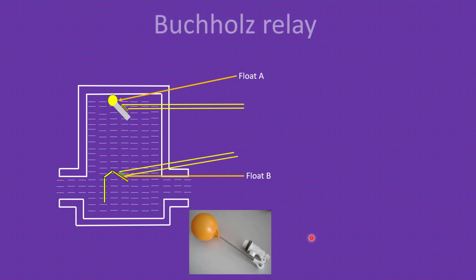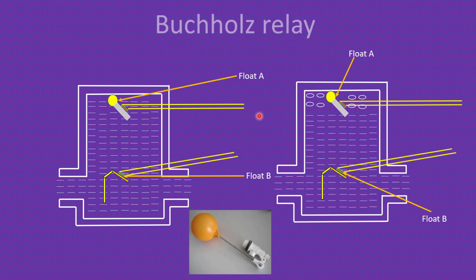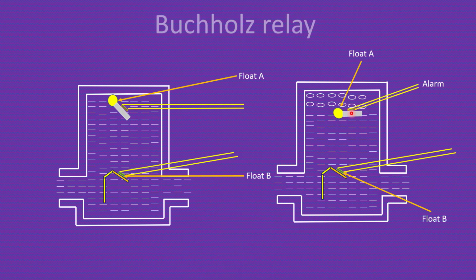What happens when a fault occurs? The transformer oil is suddenly heated. Because of that, some air bubbles will form. This oil is flowing in this direction, right? So this air bubble is trapped on the top of the Buchholz relay. Some space will be occupied by the air bubbles, so automatically the oil level will reduce. This float floats above the oil, right? When the oil level reduces, this float also will come down like this. There is a mercury switch attached to it, okay? When this comes down, these two contacts will be connected. This will trigger an alarm. When float A is activated, there will be an alarm signal. So the maintenance person or facility management person can go there and inspect the transformer. This is the function of float A.